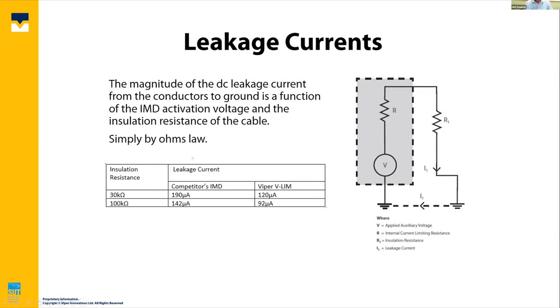And one other thing I want to just flag up now, because we will come back to this, the actual level of current that is being driven from the IMD through the insulation is a function, as you can see, of the voltage applied and the internal resistance. And depending on what the insulation resistance is and whose insulation monitoring device you select, that governs the amount of leakage current. So I've just put this table up. We will be coming back to this because the level of this leakage current actually has quite a detrimental effect on the umbilical.